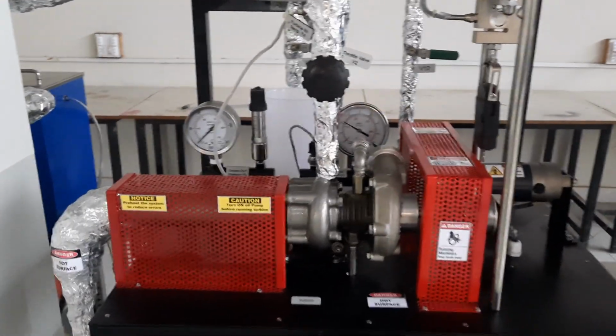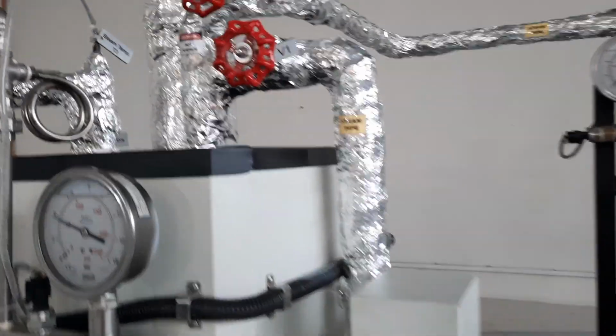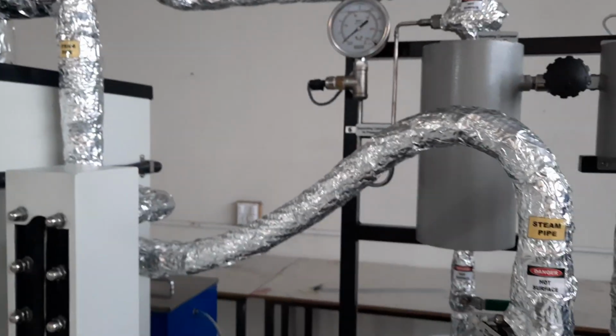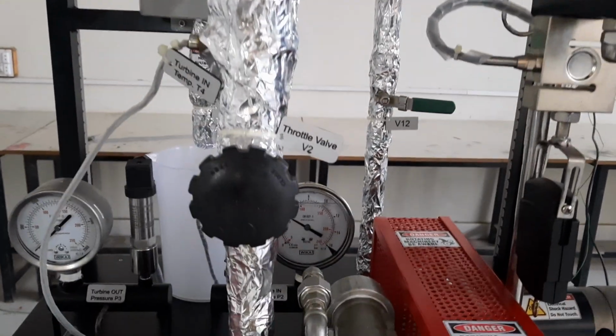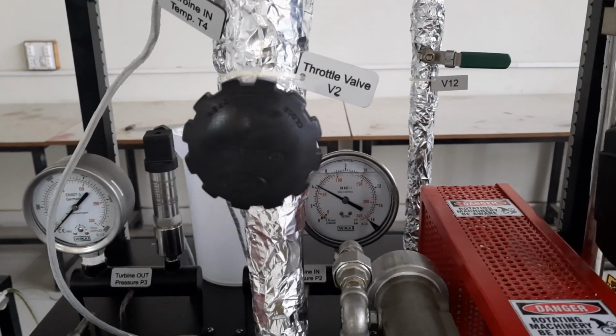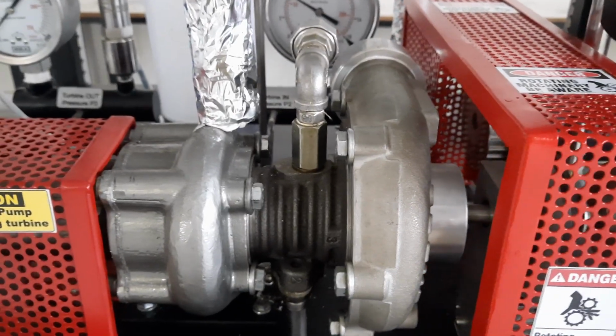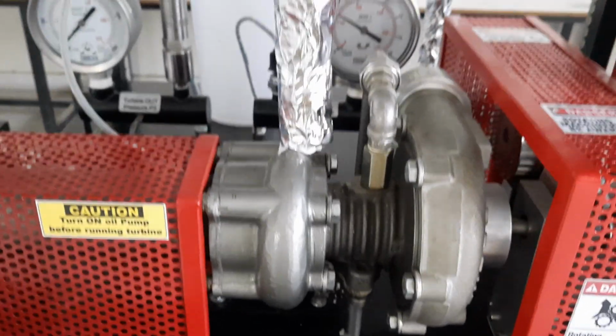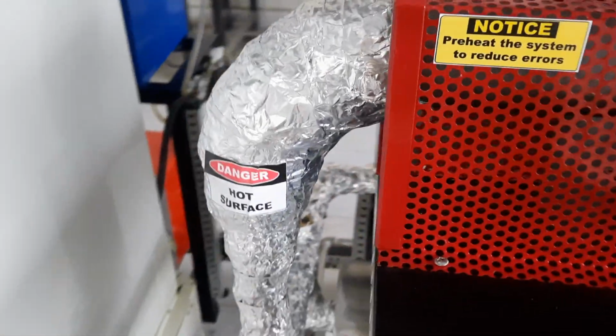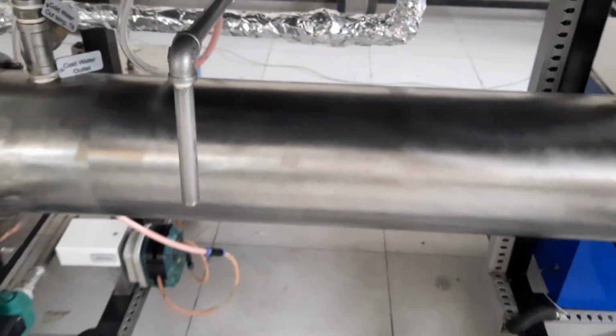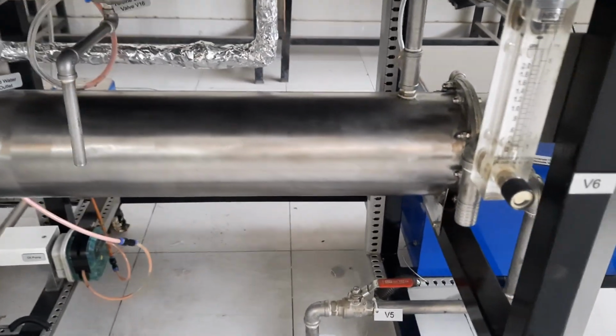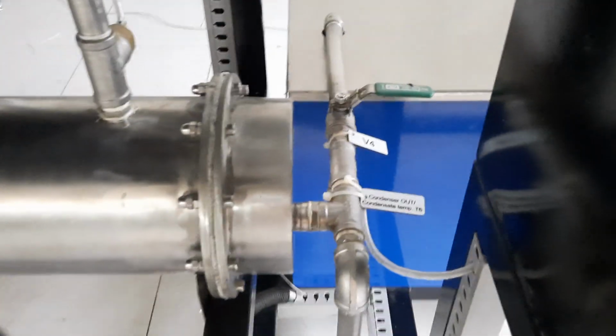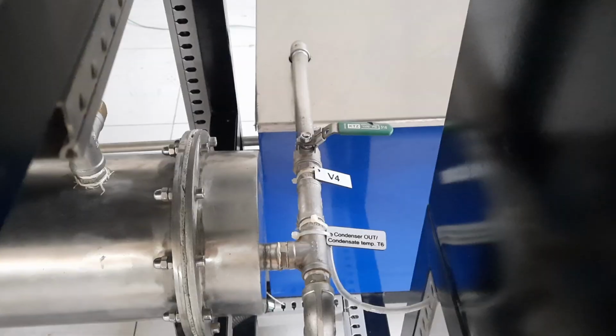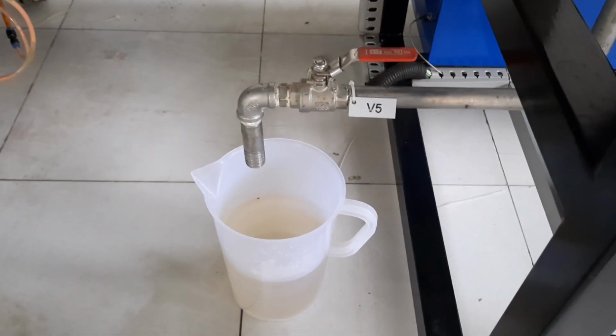To run the turbine and to find the electrical power output, you will open this valve V1. Steam will go directly through this valve to this throttle valve V2, and finally after the throttle valve it will strike the blade of the turbine. Then the steam will go through this pipe and finally into the condenser through this valve V3. The condenser condenses the steam back to its original state, water, and this water will go through the valve V4 to the feed water tank to complete the cycle, or it can also be collected through this valve V5 for the amount of condensate.